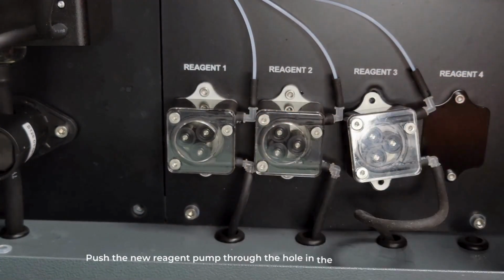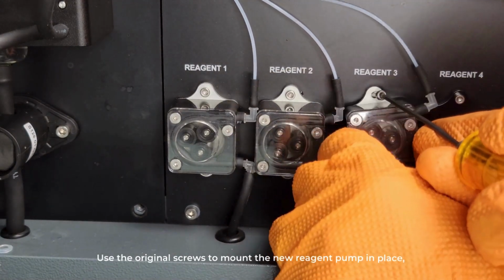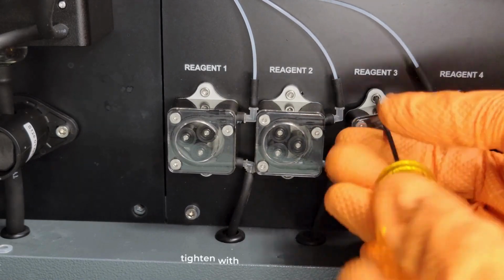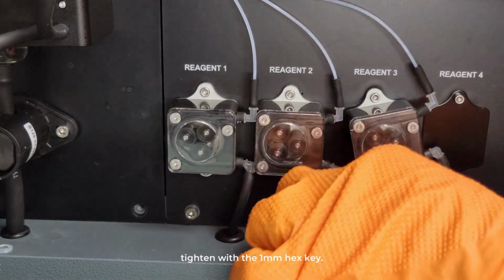Push the new reagent pump through the hole in the wet section plate, taking care not to catch any wires. Use the original screws to mount the new reagent pump in place. Tighten with the 1mm hex key.